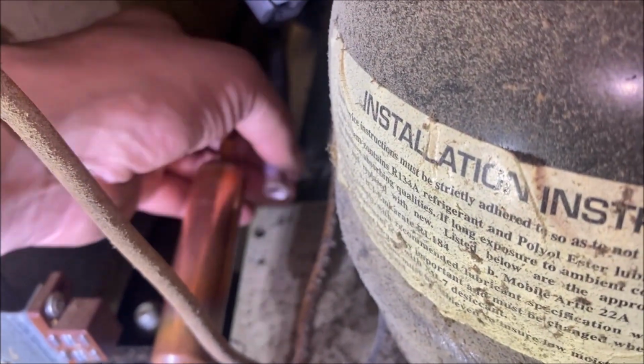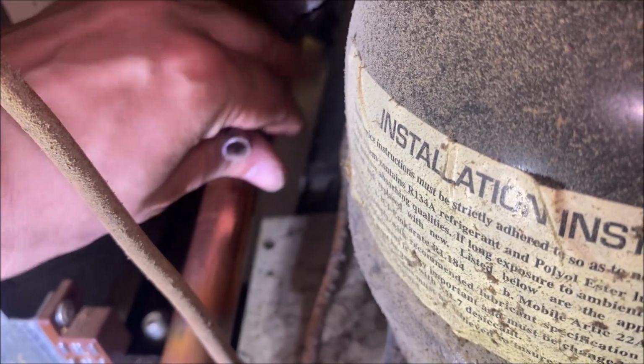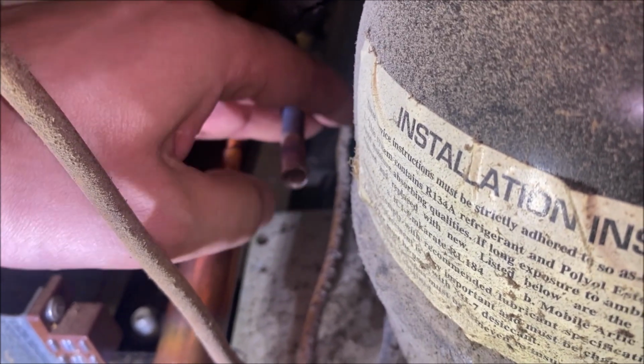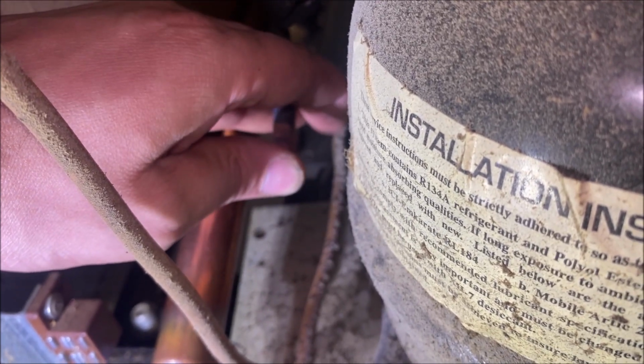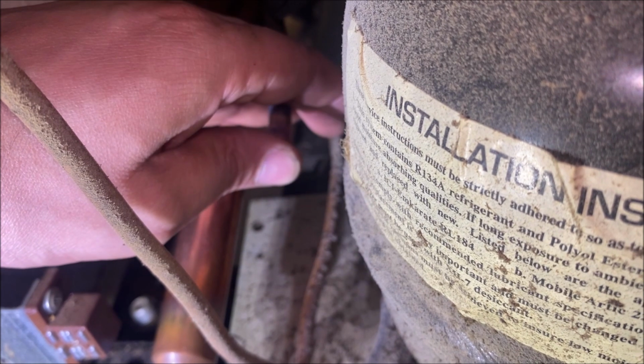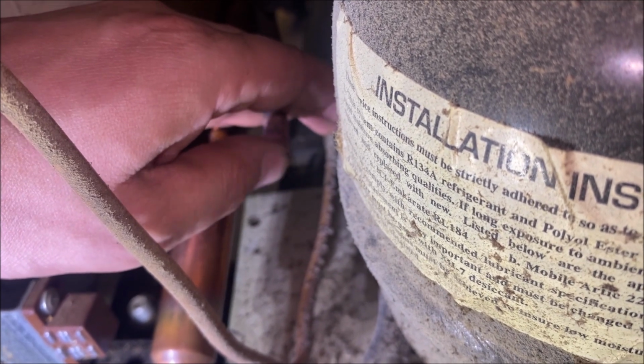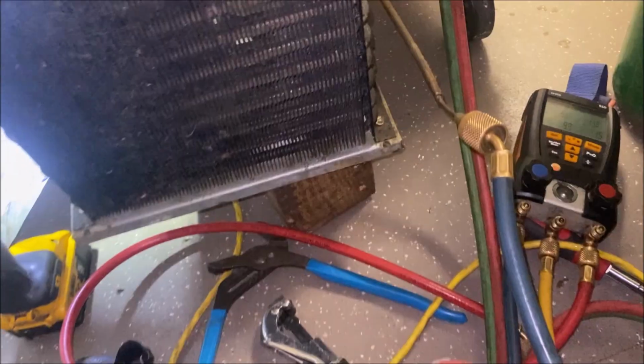All right, so I've brazed in the new coil. What I'm doing here is pushing nitrogen through. And see what pressure I'm pushing it at? Around 12 PSI, because that's the pressure we're going to use for this unit. When you're blowing in a cap tube, yeah, you can go up to 100 PSI, but where I want to test it is at 12 PSI, and we have good pressure right now.